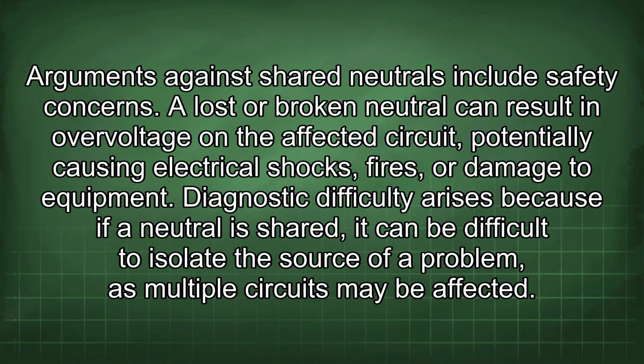Arguments against shared neutrals include safety concerns. A lost or broken neutral can result in overvoltage on the affected circuit, potentially causing electrical shocks, fires, or damage to equipment. Diagnostic difficulty arises because if a neutral is shared, it can be difficult to isolate the source of a problem, as multiple circuits may be affected.